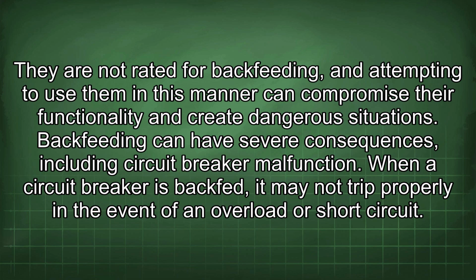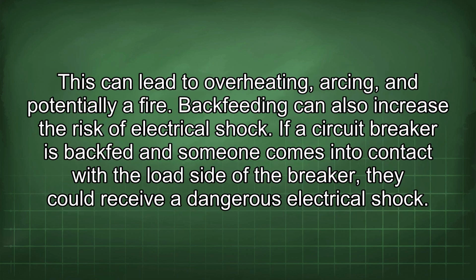Backfeeding can have severe consequences, including circuit breaker malfunction. When a circuit breaker is backfed, it may not trip properly in the event of an overload or short circuit. This can lead to overheating, arcing, and potentially a fire. Backfeeding can also increase the risk of electrical shock. If a circuit breaker is backfed and someone comes into contact with the load side of the breaker, they could receive a dangerous electrical shock.